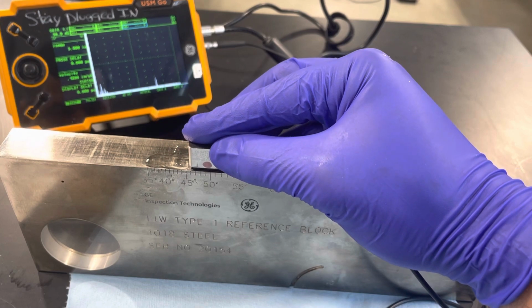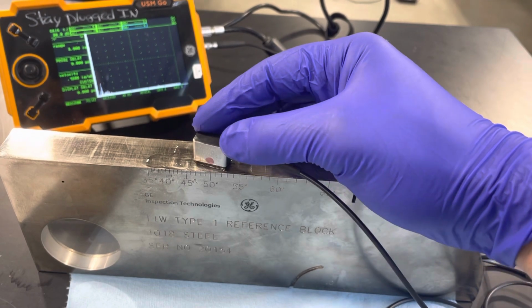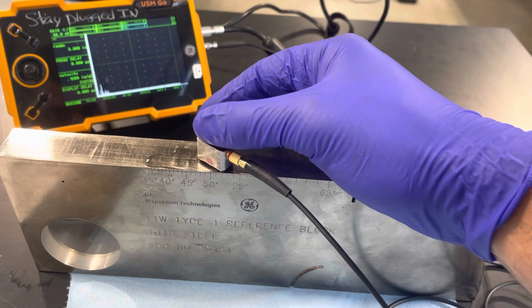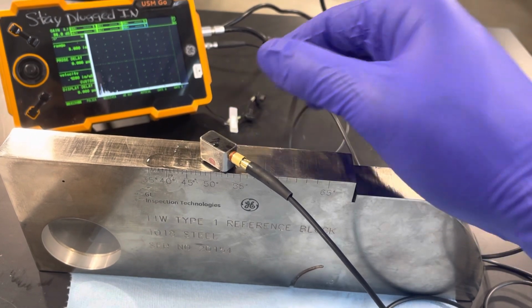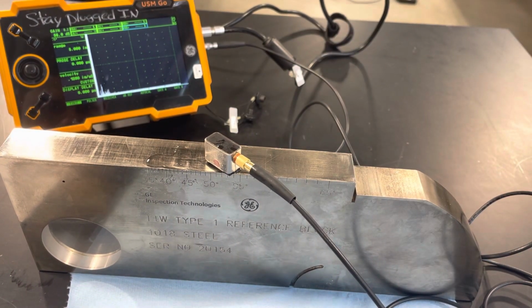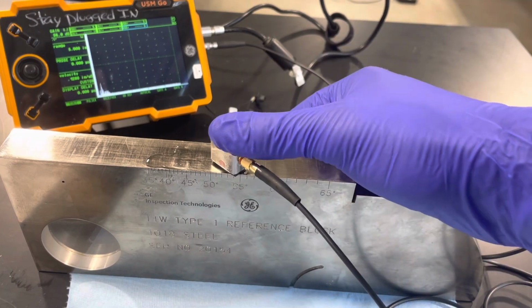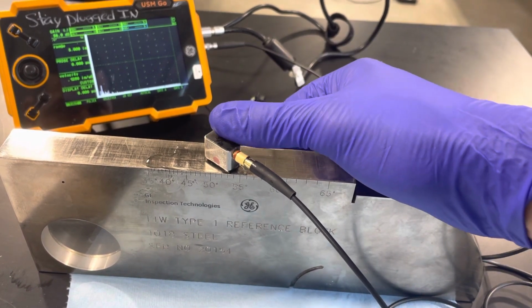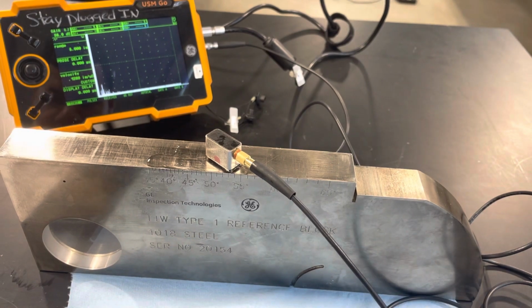And essentially all we're doing here is making sure that this transducer, which is marked at 45 degrees, is actually pushing out sound at the angle that it states, which is 45 degrees. According to procedure, we have plus or minus 2 degrees for it to be acceptable.